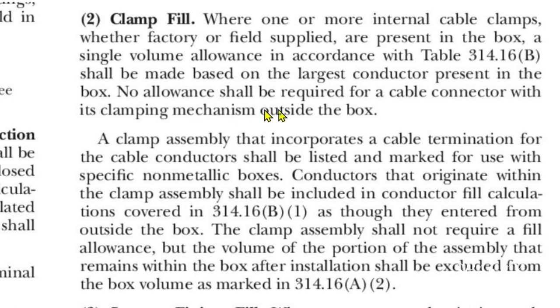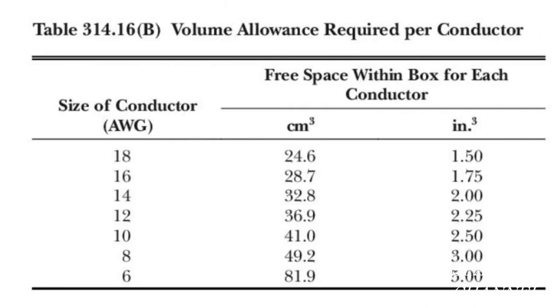No allowance shall be required for a cable connector with its clamping mechanism outside the box. Here's table 314.16B, volume allowance required per conductor. And you see where it says 12AWG conductor, which is what we had in our box example. You go over to the cubic inches area, it says 2.25. So that's our volume allowance required per conductor. And if you have a clamp that is an interior clamp, you have to add 2.25 to the total box volume fill.